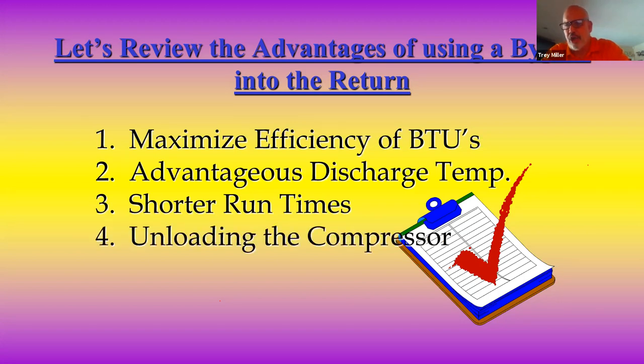Guys, I'm unloading the compressor. If I'm pre-cooling the coil, the unit doesn't have to work as hard to give you the BTUs it's designed to. This is a huge advantage and only available if you tie your bypass into the return. This allows us to increase dehumidification, reduce the runtime, and it makes your house a lot more comfortable. Because we all know the key to cooling is dehumidification. That's what makes us comfortable.